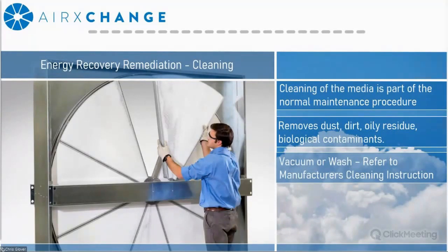Cleaning the media is going to remove the dust, dirt, residue, and any biological contaminants from the surface area. The 2 most common methods for cleaning energy recovery devices are to wash them or vacuum them. You're going to want to choose the approach that's recommended by the manufacturer. For Airxchange energy recovery wheels, we recommend that you wash the heat exchange media, as we find that gives you the best result. Our media is a segmented design, so you can actually remove the individual energy transfer segments from the wheel frame, so you can wash them outside the unit in a soapy solution.